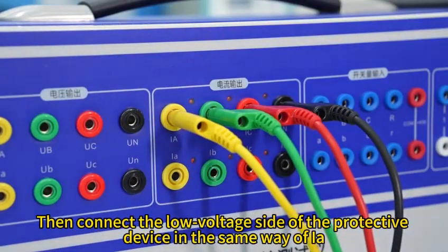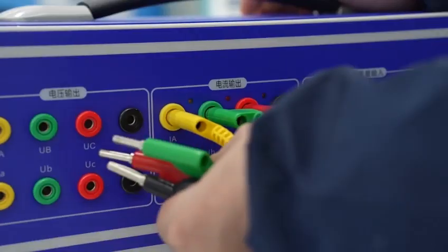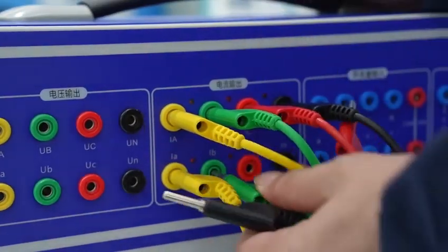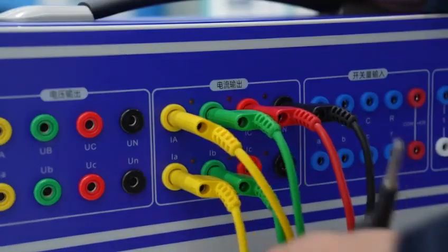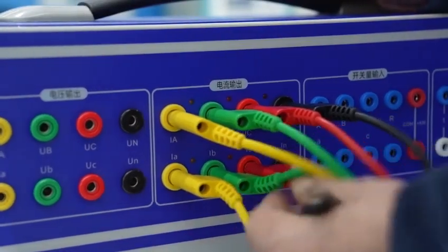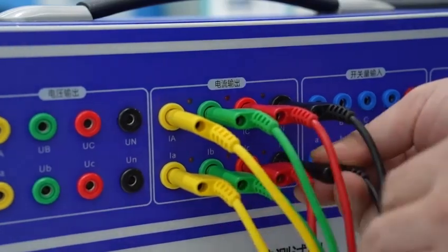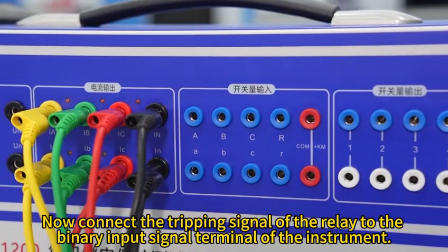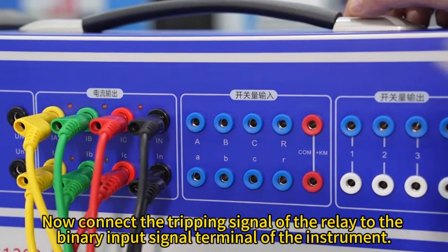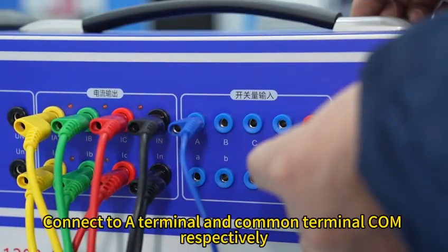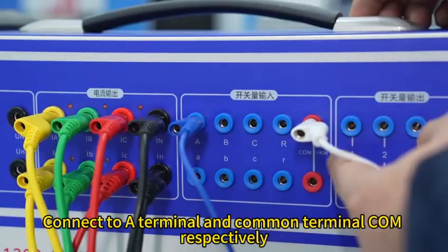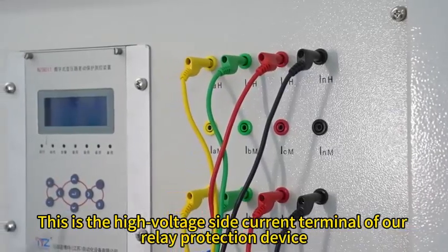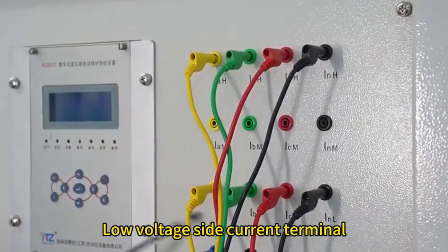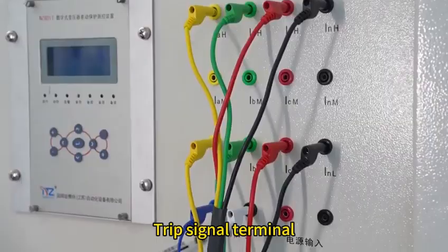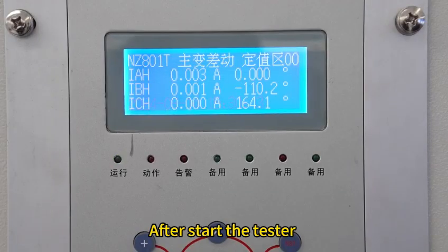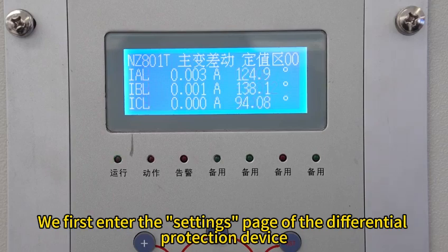Then connect the low voltage side of the protective device in the same way: IA, IB, IC, and IN. Now connect the tripping signal of the relay to the binary input signal terminal of the instrument, to A terminal and common terminal COM respectively. This is the high voltage side current terminal of our relay protection device. Low voltage side current terminal. Trip signal terminal.